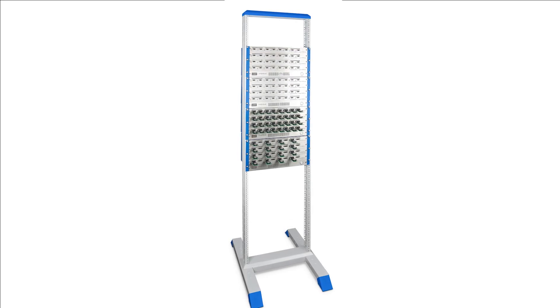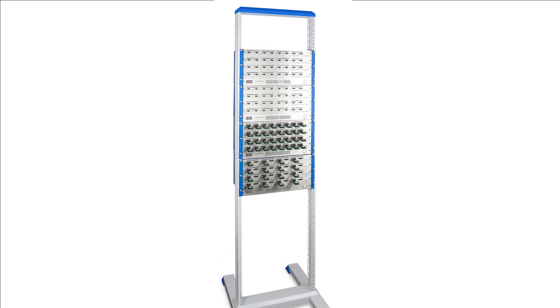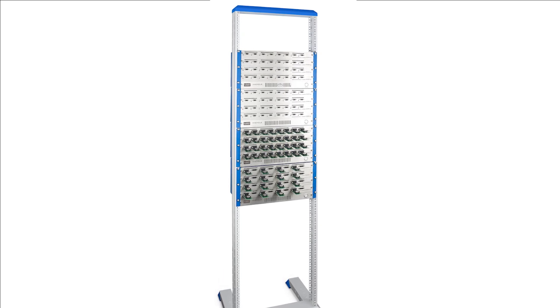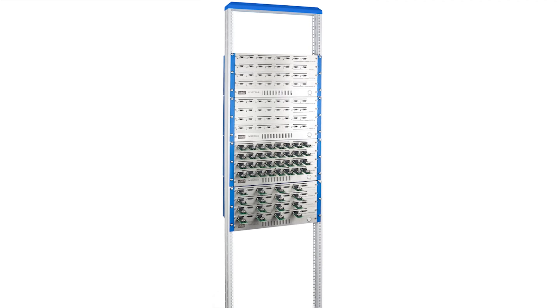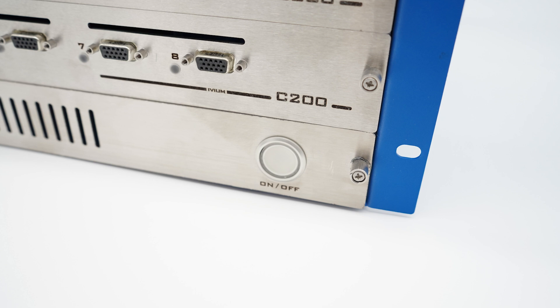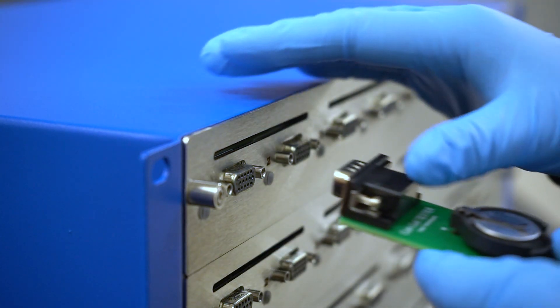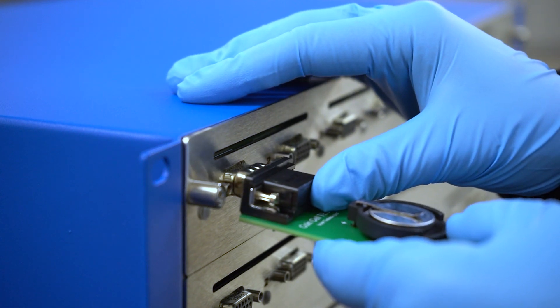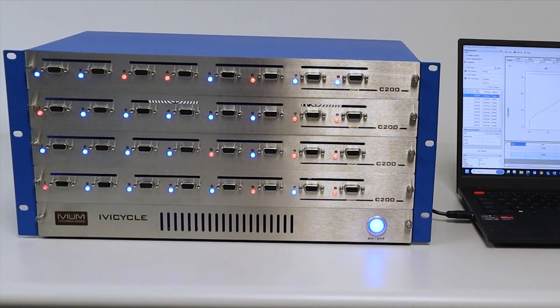Let's take a closer look at the construction of the cycler. The case is constructed so that it can be mounted in a 19 inch rack if desired, although it has feet attached for standalone operation. There is a power switch to turn the power on to the whole cycler. A USB port is used to connect to the computer for operation and data transfer. This is a connector for one channel of the battery cycler with LEDs to indicate the state of the channel.